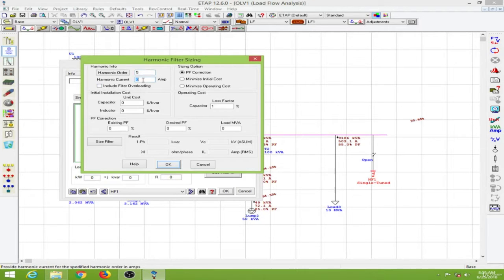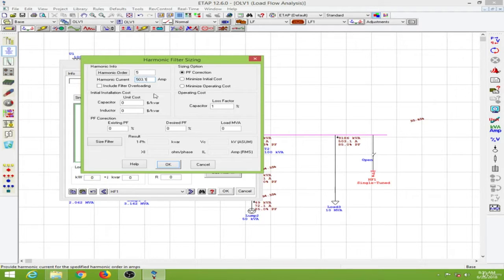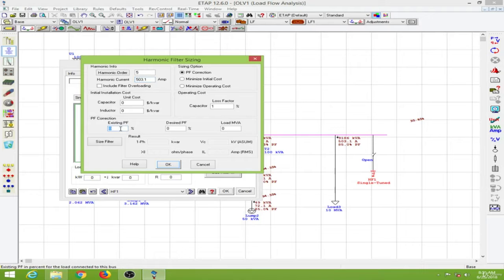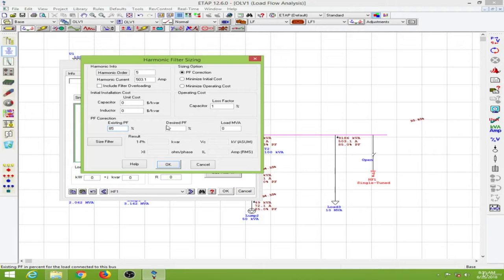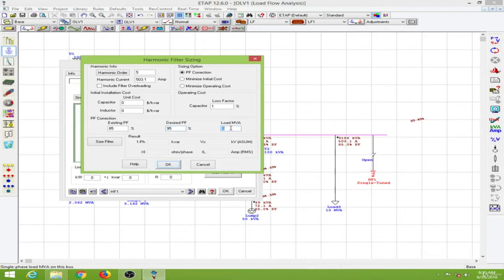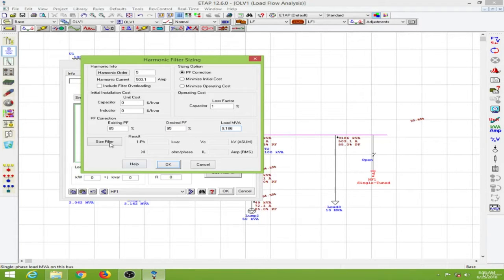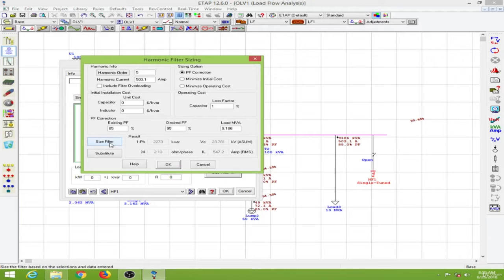The 5th harmonic current is about 503.1. This filter has a capacitor so I can use it for power factor correction. I know the power factor is about 85% from the load flow, so my desired will be 95%, and my total load in MVA is 9.186. I will go to the size filter option and substitute these values.